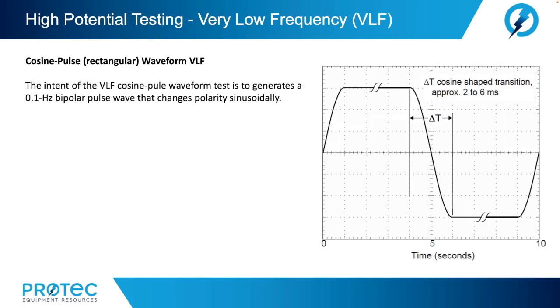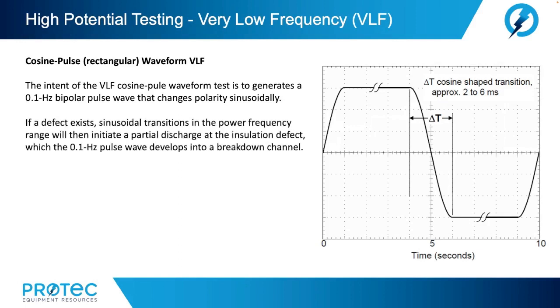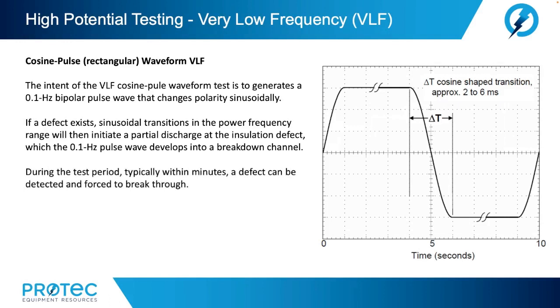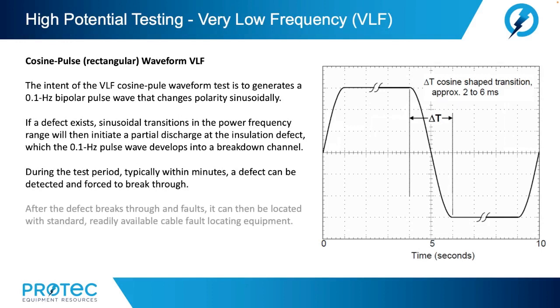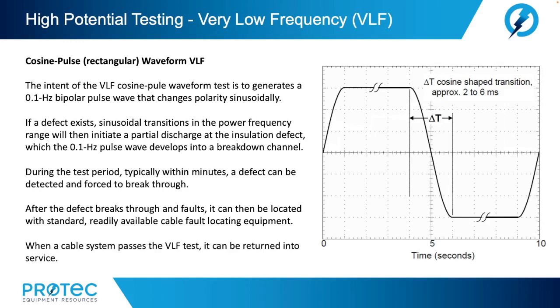The intent of the VLF cosine pulse waveform test is to generate a 0.1 hertz bipolar pulse wave that changes polarity sinusoidally. If a defect exists, sinusoidal transitions in the power frequency range will then initiate a partial discharge at the insulation defect, which the 0.1 hertz pulse wave develops into a breakdown channel. During the test period, typically within minutes, a defect can be detected and forced to break through under these controlled conditions. After the defect breaks and faults, it can then be located with standard readily available cable fault locating equipment. When the cable system passes the VLF test, it can then be returned into service.